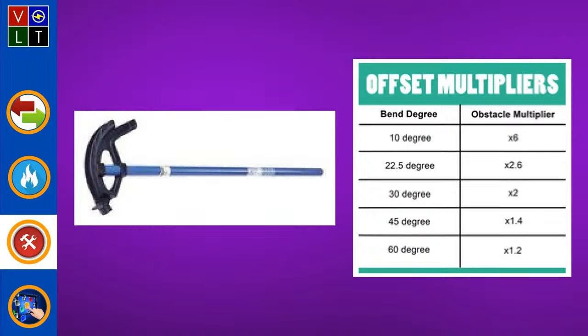So, when you're doing a 3-point saddle, you want to do a 45-degree bend right at your obstacle point and allow for your shrinkage, which is going to be 3/16 of an inch per inch of rise. So if you're trying to do a 45-degree with a 3-inch rise, then that's 3 times 3/16. So there are these multipliers in there.